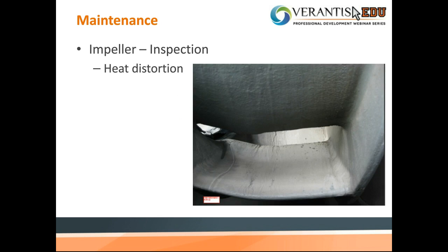So with the fans, depending on what the material of construction is, you may see some heat distortion. This particular photo shows an upset condition within the system that created a temperature spike, and you can see where this particular one is fiberglass, and the fiberglass is wrinkled due to a heat upset condition. We've seen it where it's been scorched, where the outer layer of protective corrosion protection has been worn off. It's definitely something to look at. Typically, you're aware if you have an upset condition where a temperature spike has been seen.